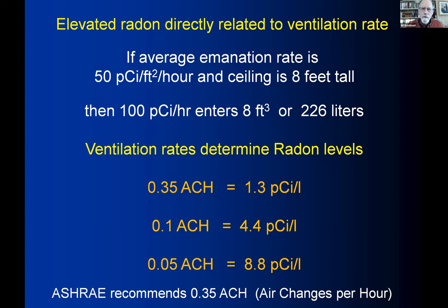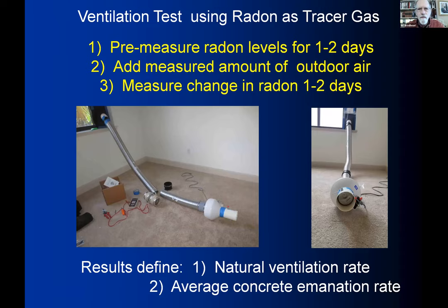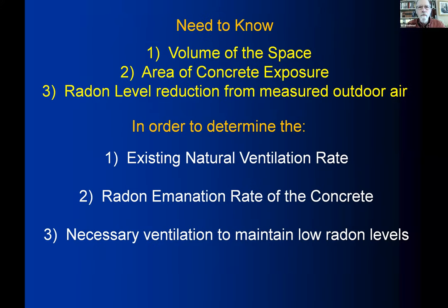To quantify the ventilation rate and concrete emanation, Bill used radon as a tracer gas. After pre-measuring radon for one to two days, he introduced 30, 40, or 50 CFM of measured outdoor air and tracked the radon change over the next two days. Knowing the space volume, concrete area, radon levels, and outdoor radon concentration, he could calculate the actual ventilation rate, average emanation rate, and how much additional air was needed.